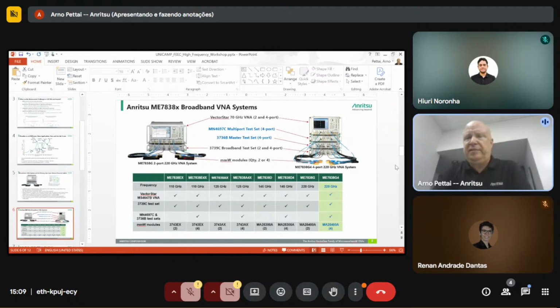So the Anritsu broadband system that's in the Unicamp lab, that is the 220 gigahertz single sweep system. So basically our flagship two-port VNA that's currently available. We also have 110, 125, and 145 gigahertz extensions in addition to the 220, but the 220 is clearly our top of the line. And it's available in 2 ports as well as 4 ports. So we basically build up these systems in a modular format so that every one of them has the same building blocks going in. And really the only thing that ends up changing will be the millimeter modules that are going to provide the frequency range.